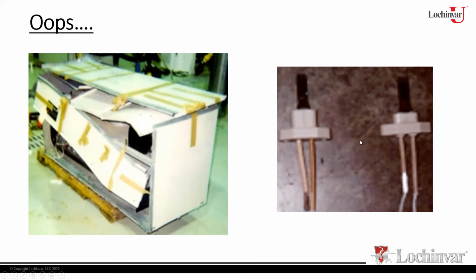So first off, you can see that there's a physical difference between the frame here. This one will not extend out over the igniter as far. But the biggest difference was the amp draw to temperature characteristic. Each one of these igniters has a characteristic. So on ours, we hit 2.75. That tells me we're getting hot enough. We start the timer to keep it hot, and then we open the gas valves. What happened on this one was we hit that amperage, but the igniter, even during that 20-second time frame, didn't get hot enough to light the gas air mixture. So it went to flame failure.